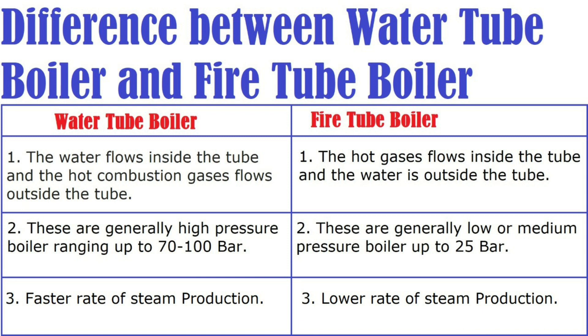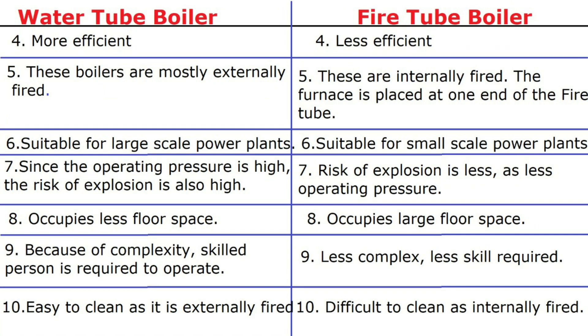There are a few differences between water tube boilers and fire tube boilers. In water tube boilers, water flows inside the tube and hot combustion gas flows outside the tube. Water tube boilers are generally high-pressure boilers ranging up to 70 to 100 bar, while fire tube boilers are low or medium pressure with a maximum of up to 25 bar. Water tube boilers have a fast rate of steam production, while fire tube boilers have a low rate. Water tube boilers are more efficient and fire tube boilers are less efficient.